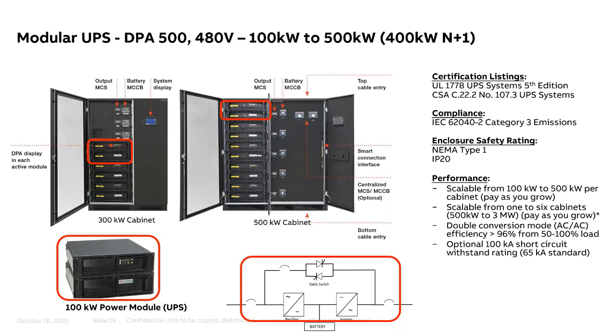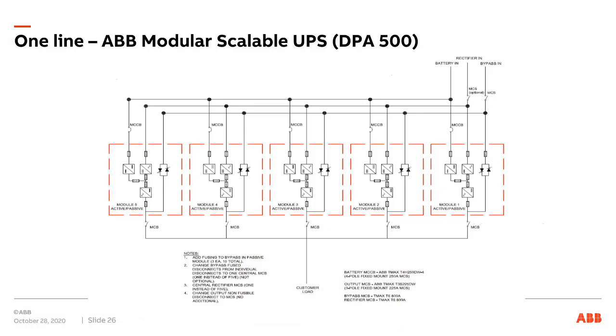But for modular UPS, it's just like monolithic. If we run out of space, if we get up to 5 and we need more power, we can parallel another cabinet to the existing one and continue to add 100 kW, or for the 208, 20 kW power modules. But they're all based on the same design.